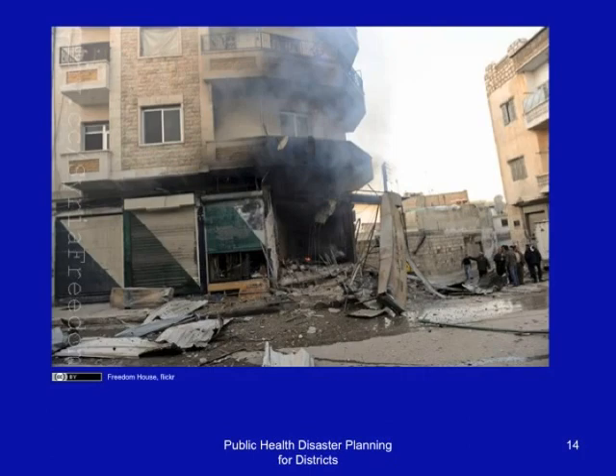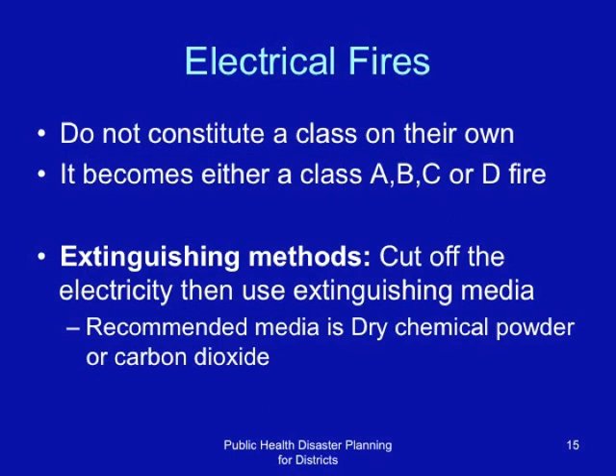Electrical fires do not constitute a class of their own, but may be either A, B, C, or D types of fires. Extinguishing involves cutting off electricity if possible. The recommended media is dry chemical powder or carbon dioxide.